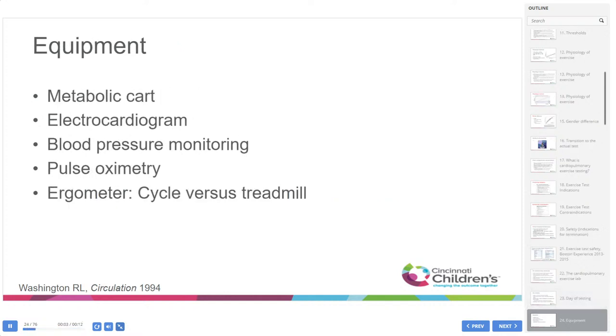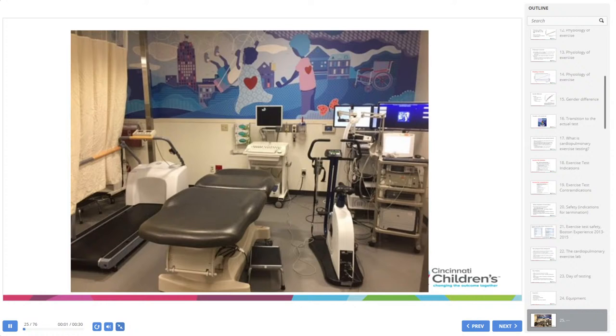Equipment needed includes the metabolic cart, electrocardiogram, blood pressure monitoring, pulse oximetry, and the ergometer — where we'll discuss whether to use a cycle or treadmill. Our exercise physiology lab at Cincinnati Children's has three distinct bays, each with a treadmill and a cycle ergometer, with the ability to position the metabolic cart based on which modality we're using. An emergency crash cart is present for every test.